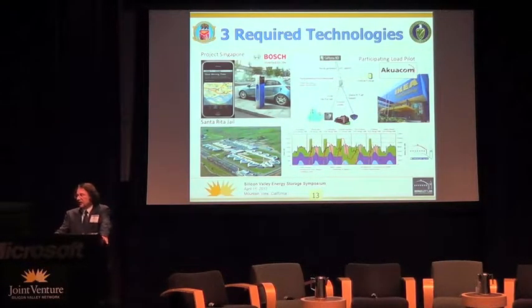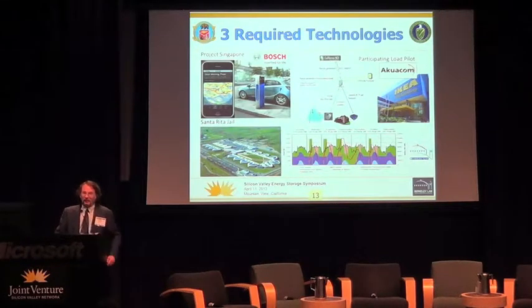On the communications side, Akuacom's contribution comes from their demand response background. They are installing a demand response automated server at a secure location inside the secure CAISO system, so it's a very secure resource. But downstream of it, between it and the base, you can use much less secure protocols — particularly OpenADR in this case. Our optimization algorithms were developed at Berkeley Lab through a related microgrid project at the Santa Rita Jail, funded by Pat Hoffman's office, which developed much of the battery use optimization work.